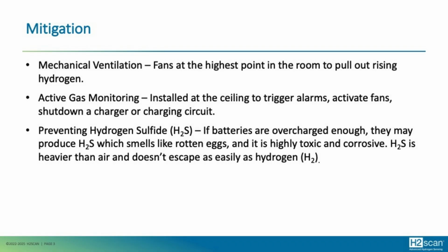This is where active gas monitoring comes into play, and these monitors are installed at the ceiling. Obviously, as I mentioned before, hydrogen rises very rapidly, so we install gas monitoring at the ceiling to trigger alarms. We don't want to install them close to the charging area. We don't want to drop them down from the ceiling so they hover above the charging area, because that would just create a lot of false alarms. So we want them very high. And then we also want them to do something.